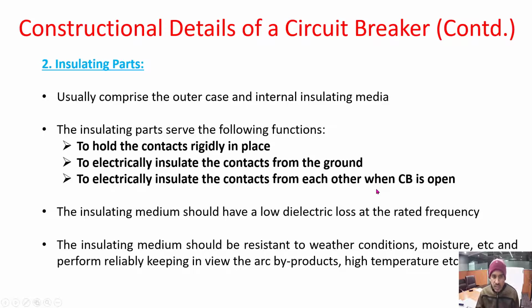When the circuit breaker is open, it means no flashover should automatically appear, so there should be sufficient insulation for that under opening condition also. So these are the three main functions of insulating parts. The insulating medium should have a low dielectric loss at the rated frequency. This is ideally required for any insulating medium. The insulating medium should be resistant to weather conditions, moisture, etc., and perform reliably, keeping in view the arc byproducts, high temperature, etc. So these are the special conditions here.